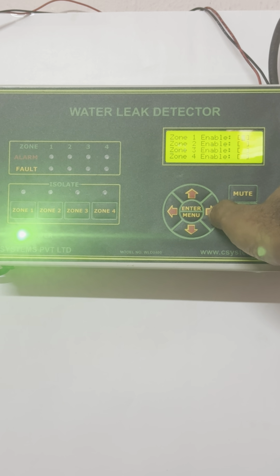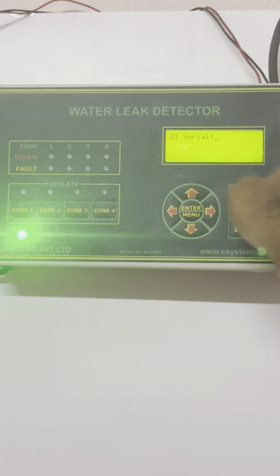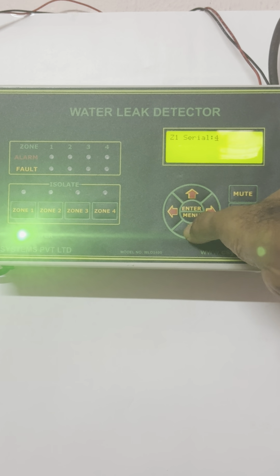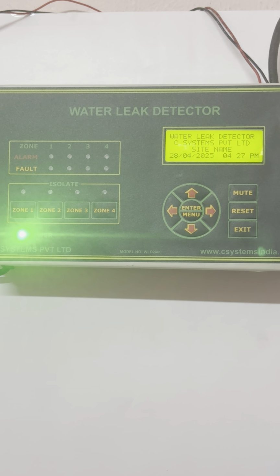First I'm going to enable only zone 1. When I press the right arrow, you will be able to see the tick mark. When I enter, it will ask for the serial number. The serial number will be printed inside the panel. In our case, it is 30026. I am typing 3, double 0, 2, 6. Zone 1 enabled successfully. Now when I go to the main menu, I can see the zone 1 healthy status.